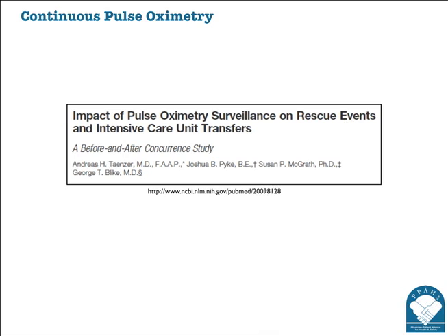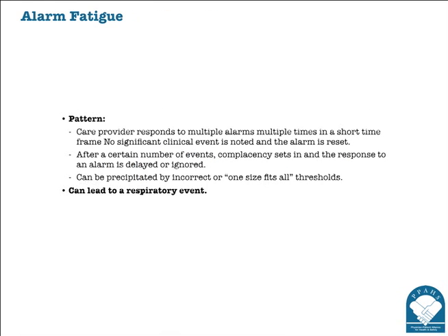There are a number of limitations. Decreased oxygen saturation tends to be a late marker of respiratory failure, not an early marker. In addition, there's the issue of alarm fatigue. Studies have shown that when pulse oximetry is deployed correctly, only about one-third of alarms are true alarms — two-thirds are false positives, contributing to the environment of alarm fatigue that nurses face. So while it can be a good strategy, for the most high-risk patients it may not be sufficient.